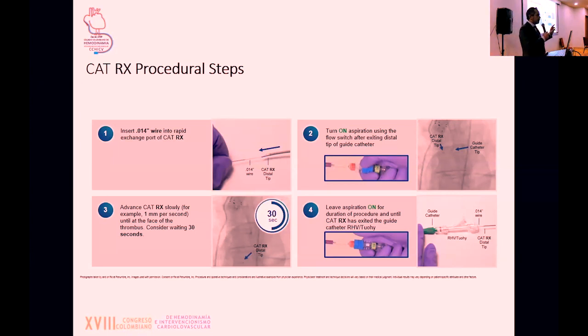The 30 seconds helps you do 2 things. Number 1, it helps create that negative suction. It requires some time for the machine to create that negative suction. And 2, you want to have the tubes all the way to the canister filled with blood, so you're able to see the dripping. That will be your guide of how far forward you need to push. You have to go back, and then slowly you push forward. And if you lose that dripping in the canister, either you sit there and give it 5 to 10 seconds so the clot may get dissolved and pushed into the catheter, or you may have to pull back to a free flow segment and then push forward.